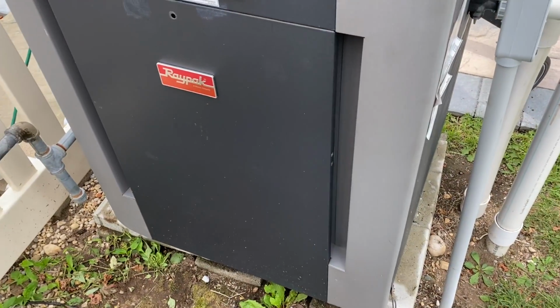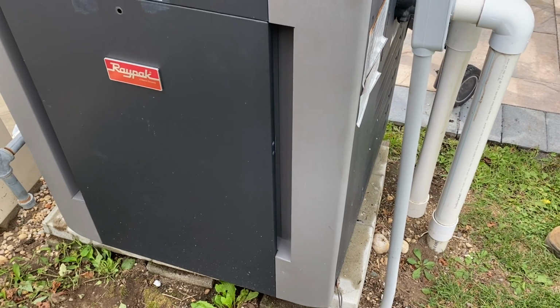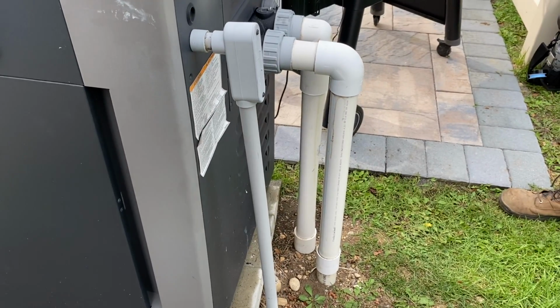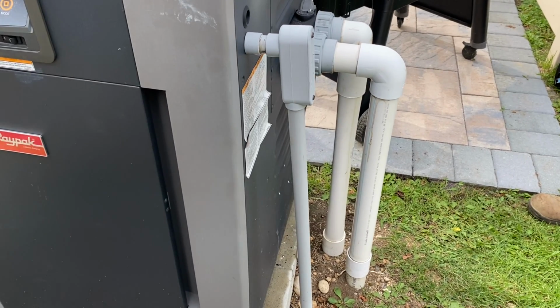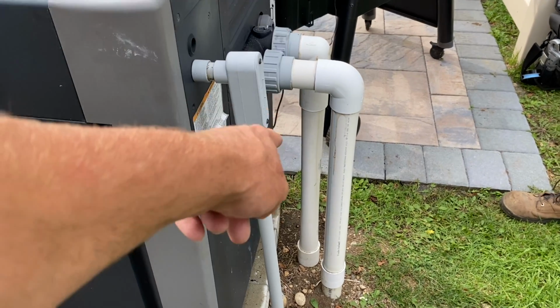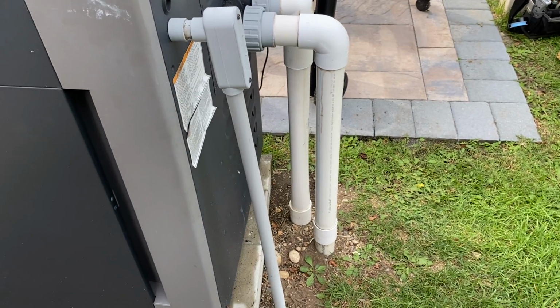What RPM are you running the pump at right now? At this moment, 2,000 RPM. Are you sure? Yep. Let's test the water temperature again on the outlet. Okay. I bet you with the lower flow, it's heating the water at a higher temperature and then deforming the piping there. And if the pipe is deformed there, God knows where else the piping is deformed.